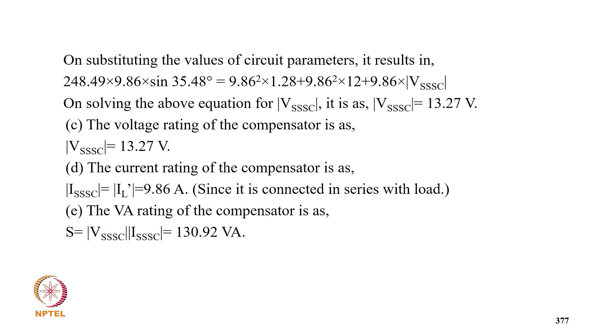Coming to example 5, a 3-phase delta connected load ZLD equal to 7 plus j3 per unit per phase has an input AC line voltage of 415 volt, 50 Hz AC supply, and base impedance of 4.15 ohm. It is also required to operate at unity power factor on the AC supply system while maintaining the same rated terminal voltage, using a VSC based SSSC.